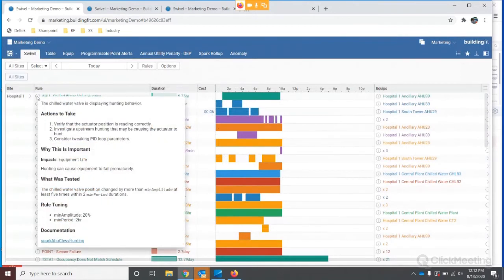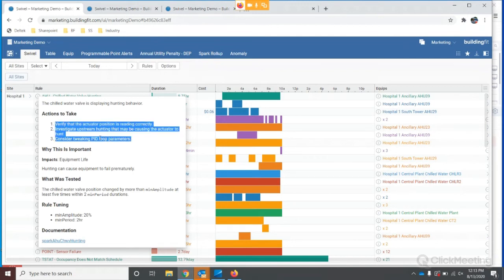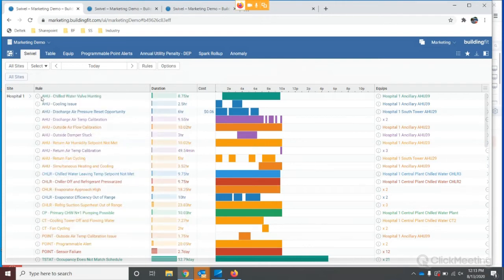We've created documentation for users to understand more from our rules than just chilled water valve hunting. What does that mean specifically? We provided actions to take for a facilities manager, why it's important, and what was tested. Then for rule tuning purposes, a list of default constants that you could modify if you had a larger deadband than what you thought was appropriate from our rule. So there's an element of modification, and using our support as needed, we can help you develop all sorts of custom rules that apply more specifically to your facility.